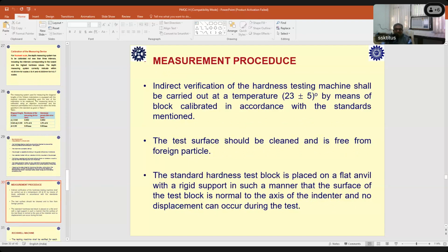So, measurement procedure: indirect verification of the hardness testing machine shall be carried out at a temperature. If you are carrying out the indirect verification, then you have to carry it out within this temperature, 23 plus minus 5. The environmental condition can also influence your hardness measurement, because of the force and the load cell, so it is better to maintain it whenever you are calibrating or checking the machine. It is better to maintain it, because a large window is there for maintaining the temperature. It is 23 plus minus 5. So in this range you can do the indirect verification of the machine.